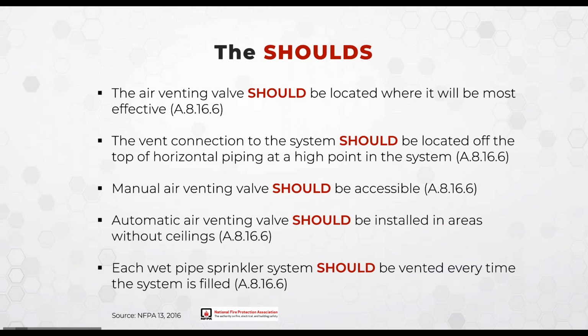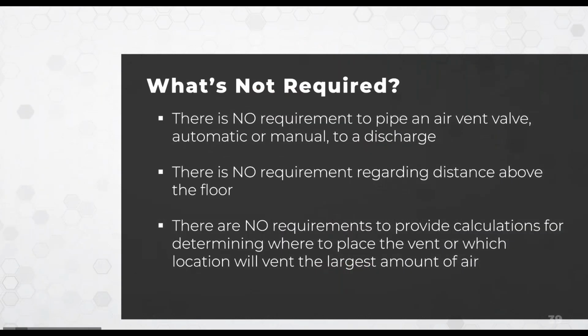If you utilize a manual air vent, you should make sure that you know where it is and that it's accessible. If you're utilizing an automatic air vent, because automatic air vents are required to have strainers, and NFPA 25 mandates that any strainer on the system be inspected, you want to avoid putting them above drop ceilings because you sometimes lose where they are. And each and every time you service the system, especially if you're using a manual air vent, you want to make sure that you utilize the air vent to get any new air out.